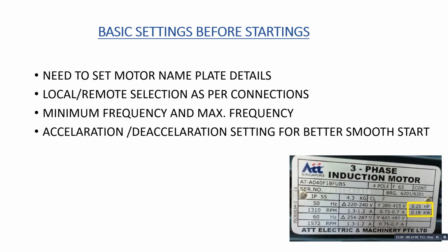Okay, by reaching from 0 speed to full speed, you can adjust this time, even 0 to 1 second, 2 seconds, 3 seconds, 4 seconds, till 50 seconds, till 100 seconds. I think you can adjust this timing. Even while stopping, it will reduce from full speed to 0 speed. The time you can adjust by accessing the acceleration and deceleration settings in VFDs. Okay, these are the minimum basic settings you have to do before starting the VFD.